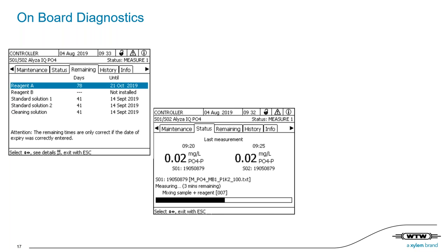Is the analyzer affected by corrosiveness in water or in the environment? So we have specifications like the pH from 5 to 9, which have to be kept. So if you have a very, very acidic solution, for example, this of course impacts the analyzer material. But if you stay within the specifications of our data sheet, that's fine.